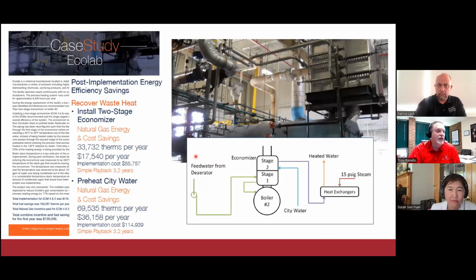This is another facility that's actually in the background here. That's a 500 horsepower boiler and a two-stage condensing economizer, which you can see illustrated in this drawing. Again, great savings. We were preheating the water going into some process heat exchangers, and they were able to run this boiler at over 95% efficiency. So it's a great concept.